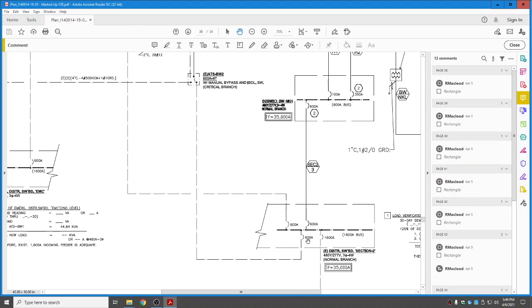But we've got one leg at 600 amp coming off of that and going over to an automatic transfer switch with a manual bypass and isolation switch. Now this normal power is going to hook up to an automatic transfer switch, or ATS BW2, 600 amp, and it's going to be a critical branch ATS. As you recall, we have 3 different branches of e-power: life safety, critical, and equipment, typically in a newer, more modern building. So there's my leg going up to the transfer switch that will typically be providing normal power.